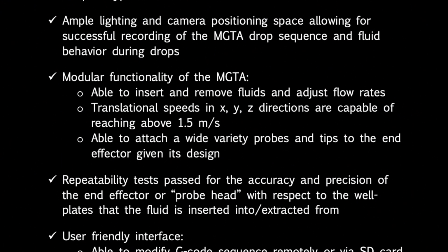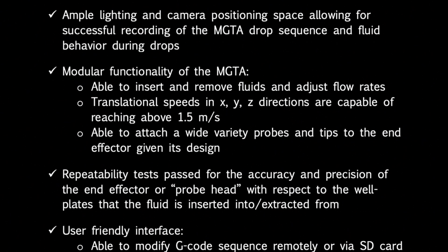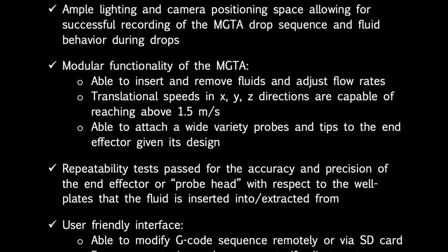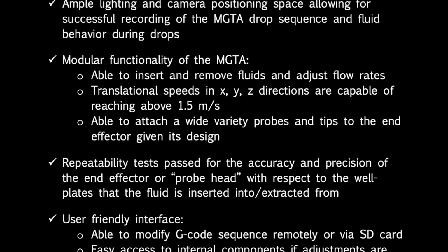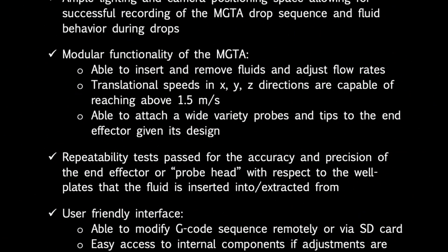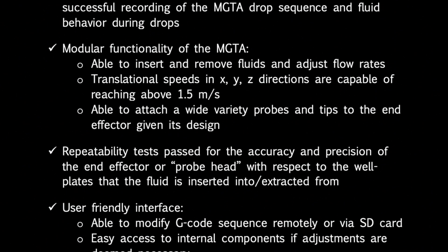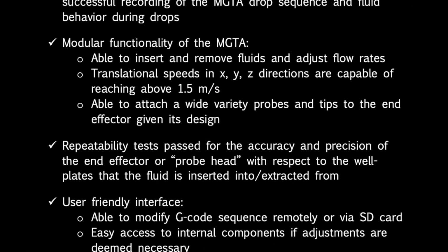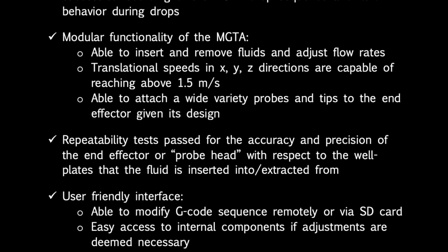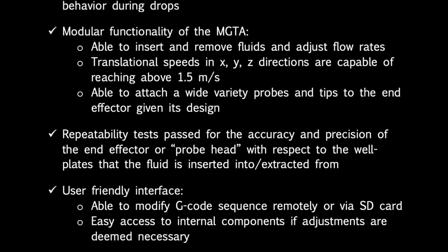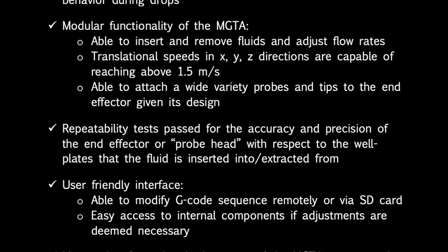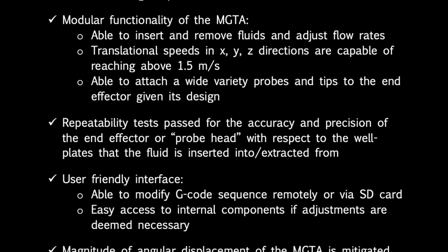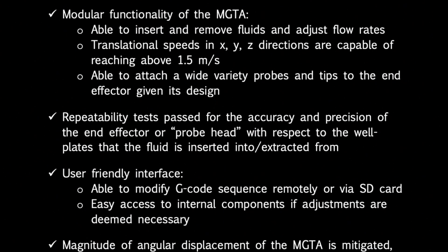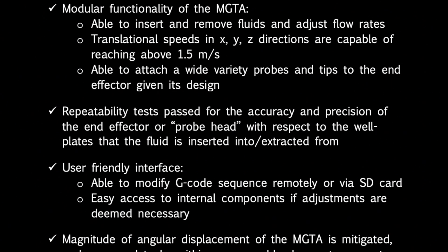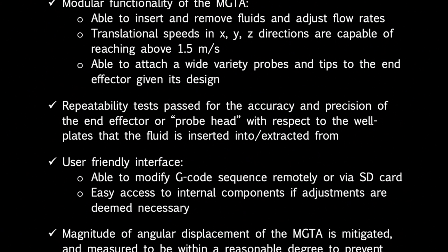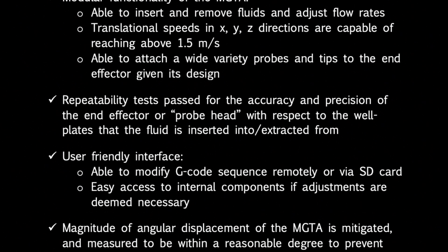soon. The MGTA is highly modular and can insert and extract fluids with adjustable flow rates. The translational speeds of the MGTA in the X, Y, and Z directions are capable of reaching above the 1.5 meter per second requirement. The user is also able to attach a variety of different probes and tips to the end effector, given the nature of its design. Repeatability tests pass for the accuracy and precision of the end effector or probe heads with respect to the well plate that the fluid is inserted into or extracted from.